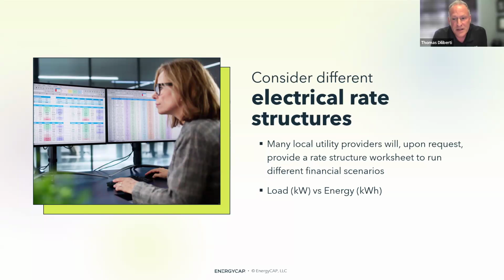Another thing, if you're unaware of this, is if you were to go back 20 years in time, many electric providers were really charging most for energy use and very little for load. That's changed over the course of the 20 years that I've been in the industry. Now, most of the electrical rate codes, you're paying more for load than you are for energy use. But based on the size of the building and the utilization of the building, you need to do your homework on this, particularly if you're doing a lot of building improvement or you're really wanting to understand the benefits of spending some money in the short term in order to fix some things. These spreadsheets, once again, that come from the vendor could be a really useful tool for understanding the benefits to you in your organization.